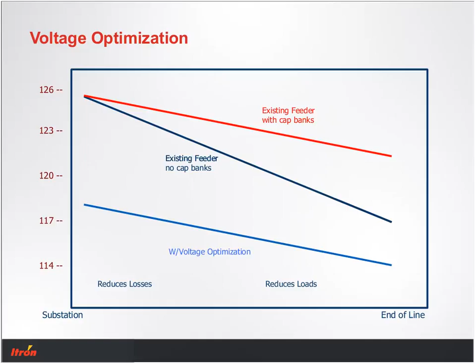So that enables me now to do yet another thing, which is bring that entire curve down. As I do that now, I still stay above 114, and I'm at about 118. So I still have that 4-volt drop, but I've reduced the entire curve. I've brought the entire curve down by, this is an exaggerated example, but 8 volts. So that would be 4 times my business case, so I would now be at 20 plus megawatts. That's not a realistic scenario, but just something to highlight for this voltage reduction and the impact that you can have, bringing that curve down.